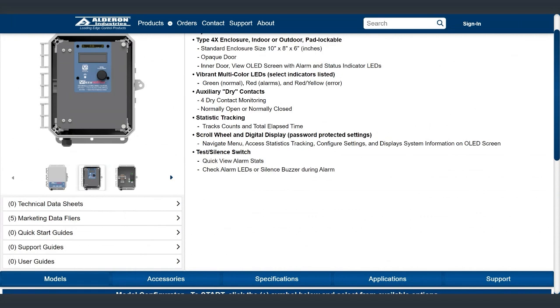And in here it has 4 inputs. You can connect any 4 inputs. You could make your connection from your contactor here, or from a float for a high-level alarm, or auxiliary contacts. And then this would send the alarm signal out wirelessly. So you can get Wi-Fi or cellular notification. So we have the 4 dry contacts, normally open or normally closed.